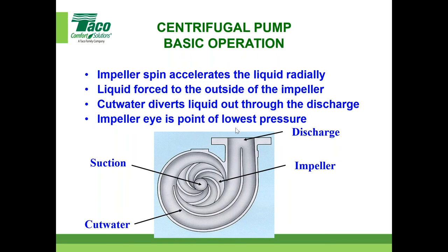Thanks. Super. And here's another cutaway. There's that suction. There's the cut water, right? You can see it diffuses. It sends the water out the impeller, out the discharge. The impeller eye is the point of lowest pressure. Kind of makes sense, right? That's where it's coming in. And then as this spins radially, the water is diffused out, spun out, forced to the outside of the impeller. And that's how it's diverted out. So pretty straightforward.